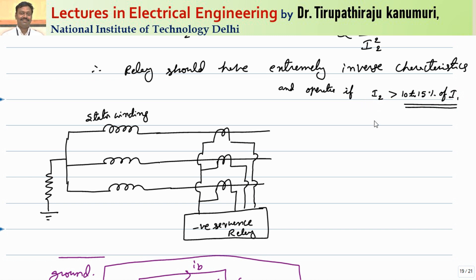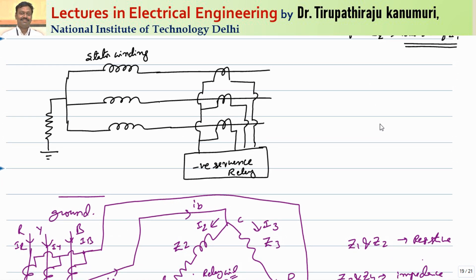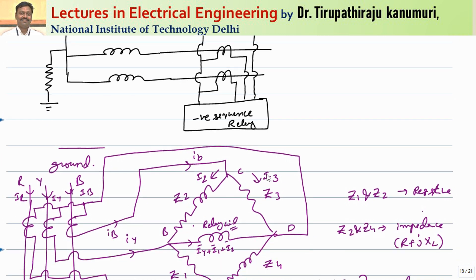For detection of negative sequence currents, three CTs are connected to the stator winding in star configuration — only one side is required since this is not differential protection. These are connected to a negative sequence relay, which operates a relay having extremely inverse current characteristics.